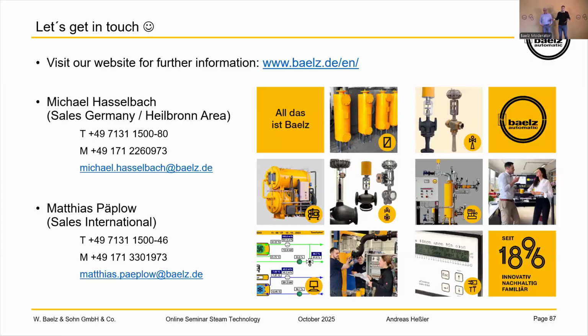And this is a lot. I mean, 14%. You can also calculate it on your own, or maybe we can do a calculation example and show you the difference. 14% in steam saving is a lot, depending on the power of the system. By 590, we can also save between 10 and 15%. It depends a little bit on the process data, but in the standard, it's round about that.